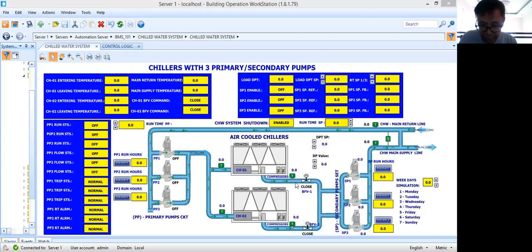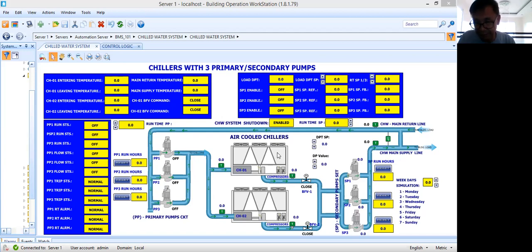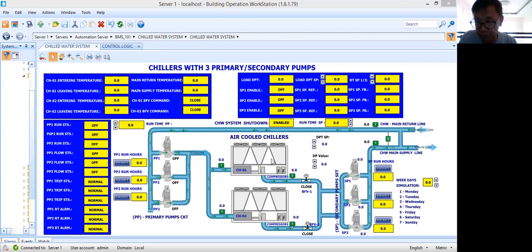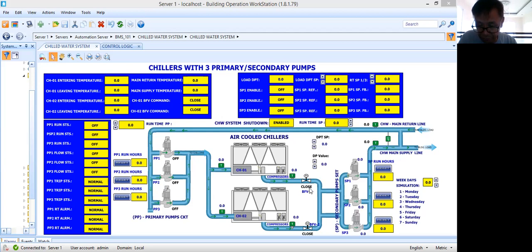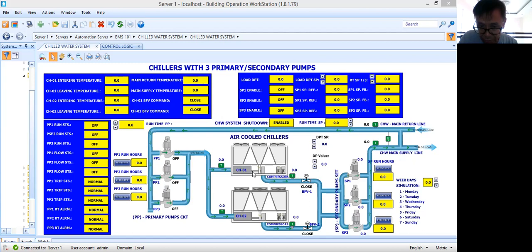What we need to do is just to start the chillers. If you will be the one to start the chillers, you need to get the chiller status — if it is in auto or in manual, it should be in auto. If you get the auto status from the chiller, then there's no problem. Then you can open the butterfly valve, start the primary pump, then start the chiller. First you open the butterfly valve, then run the primary pump so that there will be flow in the cooler of the chiller, because if there is no flow, your chiller will shut down.